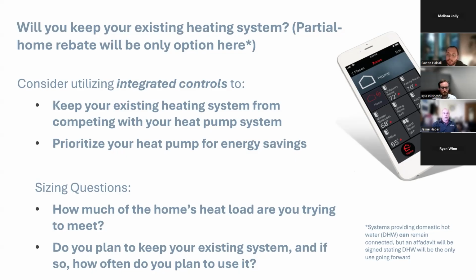So for example, if you were looking at a system that didn't have a very good capacity maintenance ratio, but it's still the system you really want to go with, cool. In that case, maybe it makes sense to keep the oil or propane in the background and say, below this certain temperature set point, which we can adjust, we'll use the oil system. At least that way we'll save oil for half the winter by using the heat pumps when it's a little warmer out.